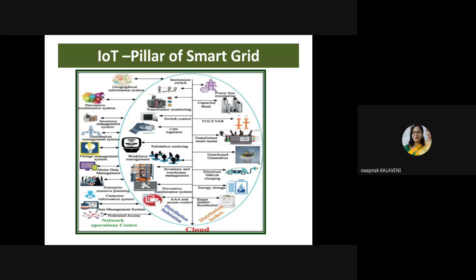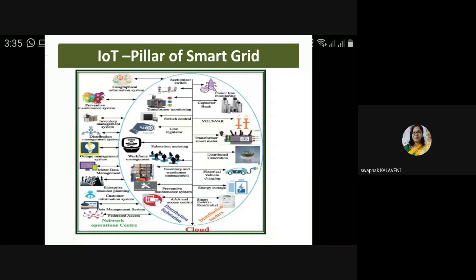Every microsecond, we are monitoring the current. At some point of time, say in the evening around 7 o'clock or midnight about 11 o'clock, because of the air conditioner during summertime, or because of the evening loads during normal days, if the evening load is very high, the transformer may get overloaded during peak time. Then what should we do? At that point of time, how can we bifurcate? Can we put an additional transformer or can we increase the capacity of the transformer? Such decisions we can take based on the input we are receiving from the transformer to the control room.